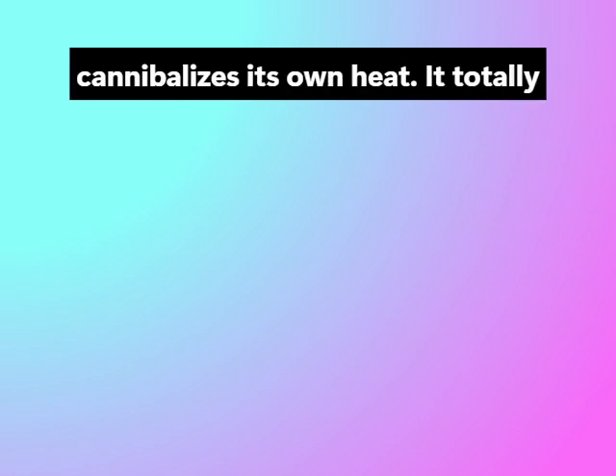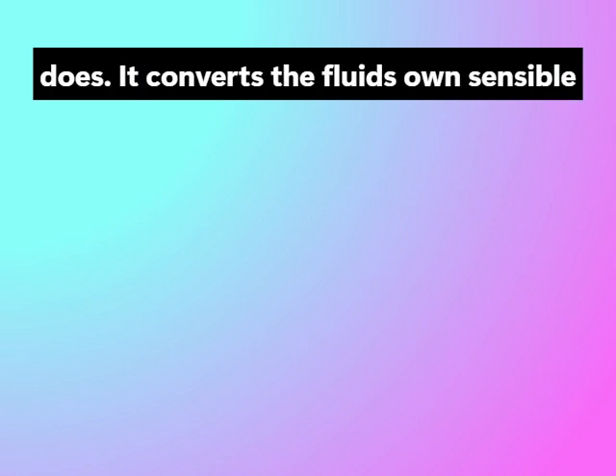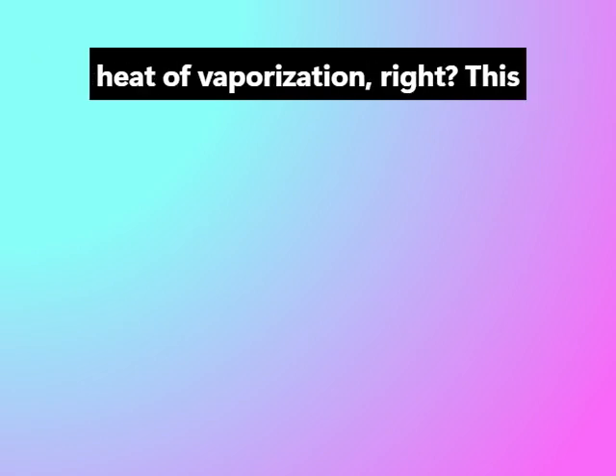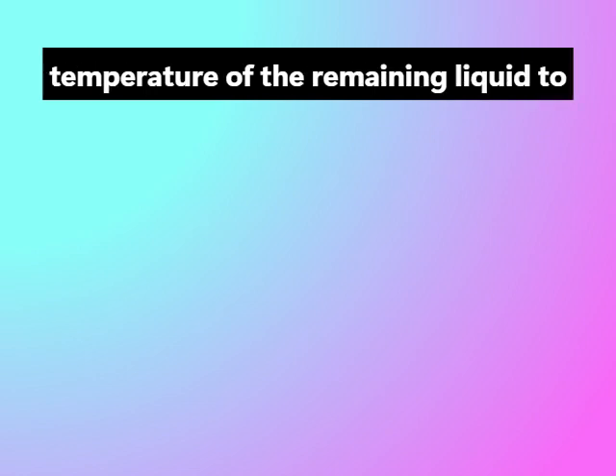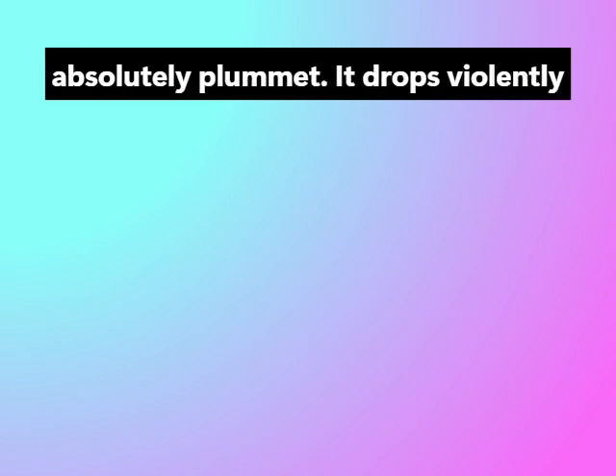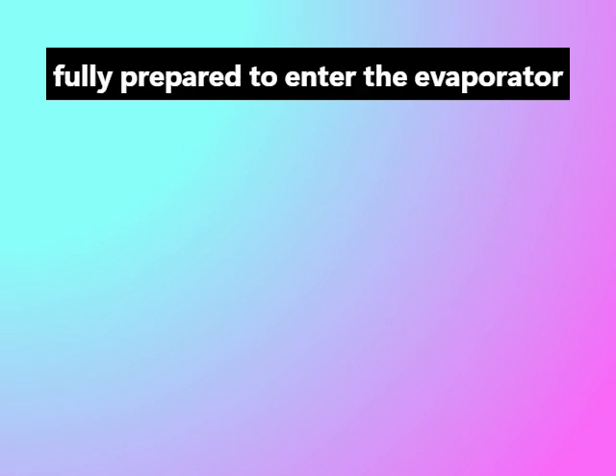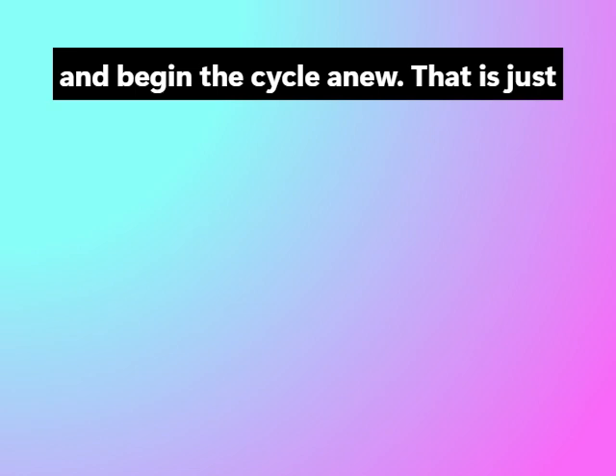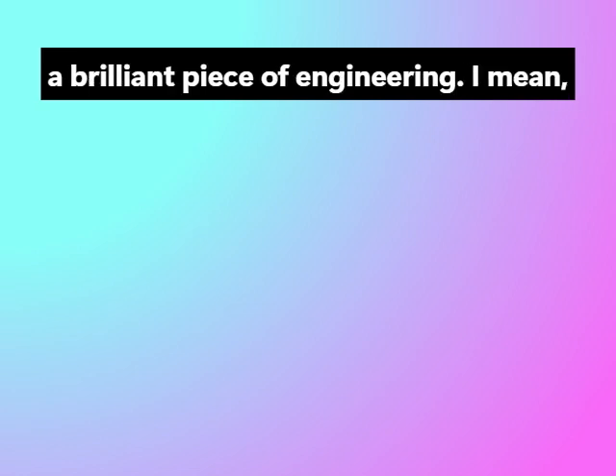It cannibalizes its own heat, converting the fluid's own sensible heat, the heat you can measure with a thermometer, into the latent heat of vaporization. This internal energy theft causes the temperature of the remaining liquid to plummet, dropping violently back down to a 0-degree, low-pressure state, fully prepared to enter the evaporator and begin the cycle anew. That is a brilliant piece of engineering.